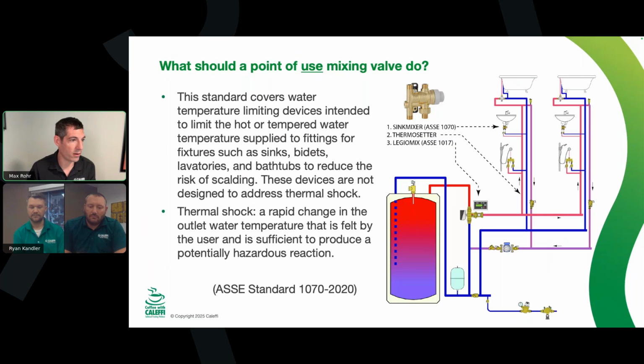A big point of distribution mixing valve will still do that job, but if you had a sink that was 8 feet away, it's not the same animal. You'd want a point of use mixing valve to make sure nobody gets scalded.